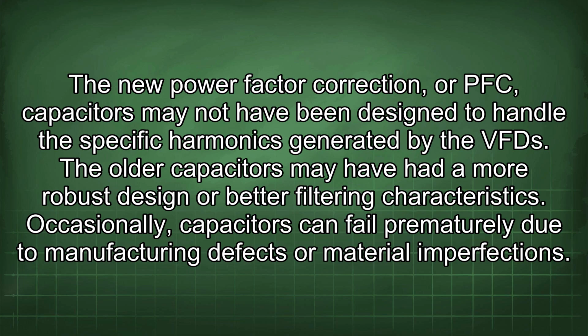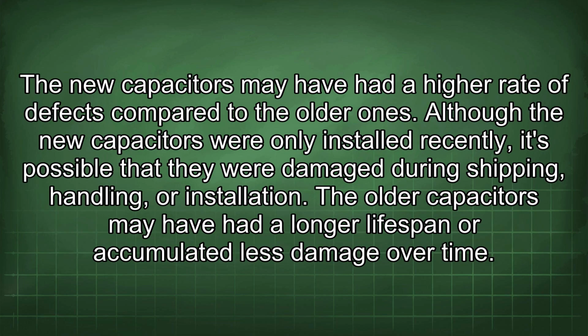Occasionally, capacitors can fail prematurely due to manufacturing defects or material imperfections. The new capacitors may have had a higher rate of defects compared to the older ones. Although the new capacitors were only installed recently, it's possible that they were damaged during shipping, handling, or installation. The older capacitors may have had a longer lifespan or accumulated less damage over time.